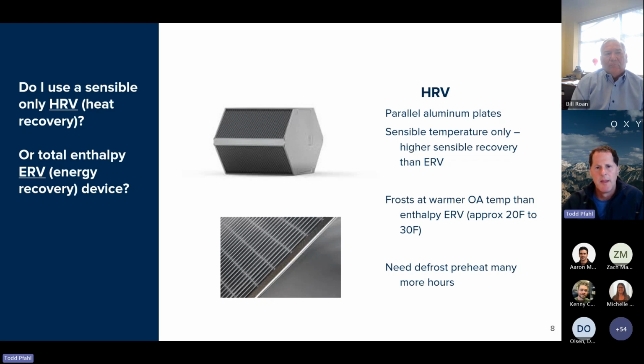Also allows us to have a low profile as we put these into air handling units and be able to put into very tight spaces, up into ceilings and walls, which you'll see there, which helps to take advantage of decarbonization. But when we look at heat exchangers, there's basically two flavors. There's HRV, which is a heat recovery device, and an ERV, which is an energy or enthalpy recovery device. For HRVs, basically they are just parallel sheets of aluminum plates that go the length of your core, and they transfer sensible temperature or sensible energy only. So only temperature gets transferred, no moisture gets transferred. You may think in a dry climate like you have in Denver, you may not need moisture transfer. They are very efficient at transferring sensible temperature.